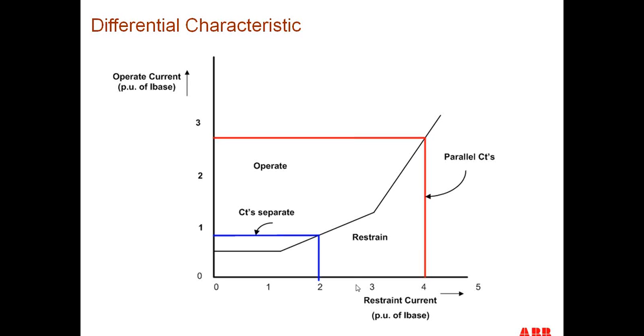If I had the two CTs added together, and I had 2 per unit current coming from each one of the CTs, then my restraint current would be here at 4 per unit, and my operate current would be, because I would be way out here on the curve, up around 2.8 or 2.7 per unit operate current.